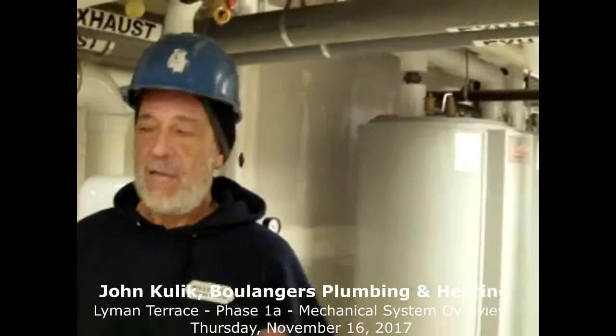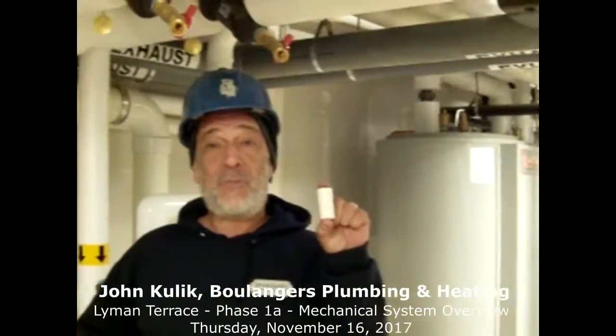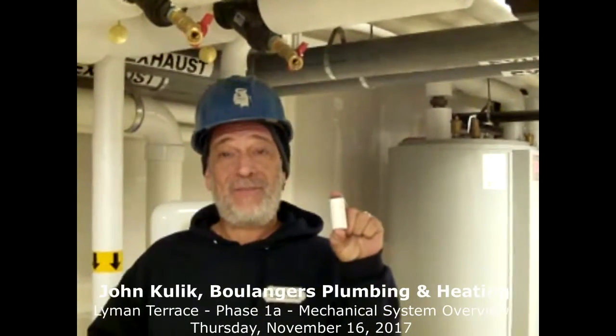Again, spring comes, it warms up outside. This device shuts down the pumps and tells the boilers, no matter who says what, don't produce any heat. You're only armed now to make hot water. Wow, so those outside sensors are critical. Absolutely. If it gets to a point also where, let's say, we have our shoulder months.